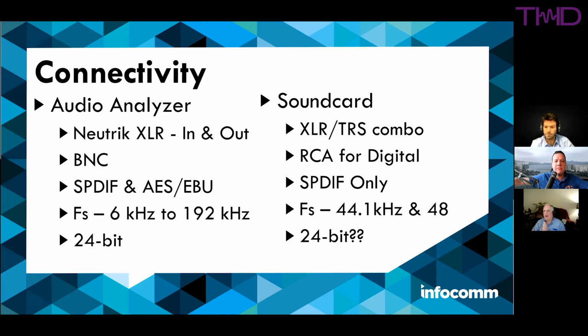Not all sound cards or digitization devices are created equal. Without naming names, I've measured sound card devices where the specs claim a 24-bit converter, and using some specialized test signals in our AP analyzer, we find it's really only 22 bits or 21 bits. So the spec sheets might say 24-bit, but depending on what's going on, what matters is the ENOB, the effective number of bits. That's a critical spec to know, and it may or may not be listed in sound card specs.